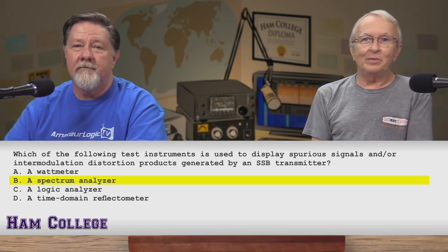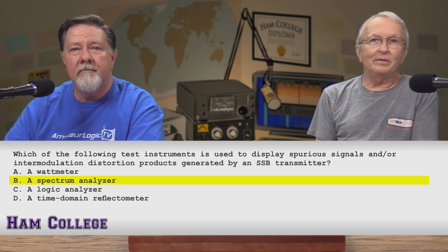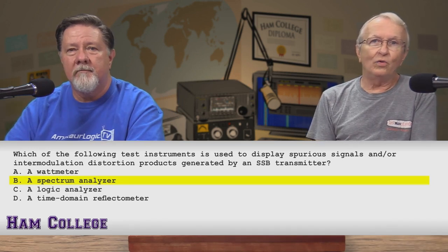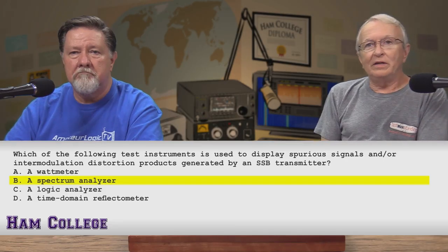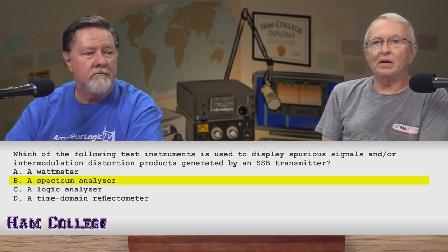No, what a time domain reflectometer does is you can hook it to a transmission line or a piece of wire, and it shoots a pulse down that wire, and the thing measures how long it takes for that pulse to go out there and hit something and reflect back to you. You'll also see how much of a reflection there is. That's why they call it time domain, so you can tell on a piece of transmission line, say it's a 100-foot piece of line and you've got a splice in it at 50 feet, and you got water in that splice. The time domain reflectometer can tell you at 50 feet out, all of a sudden the impedance jumps way up or goes way down or something changes. It's something you would use to tell how far down a piece of transmission line an issue is.